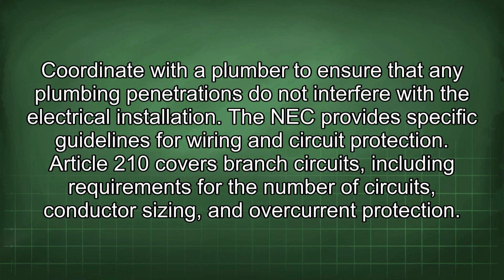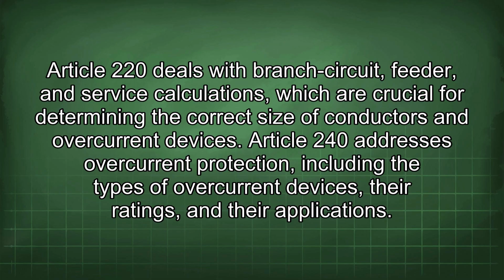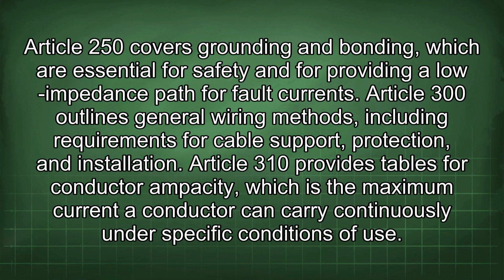Article 210 covers branch circuits, including requirements for the number of circuits, conductor sizing, and overcurrent protection. Article 220 deals with branch circuit, feeder, and service calculations, which are crucial for determining the correct size of conductors and overcurrent devices. Article 240 addresses overcurrent protection, including the types of overcurrent devices, their ratings, and their applications. Article 250 covers grounding and bonding, which are essential for safety and for providing a low impedance path for fault currents.